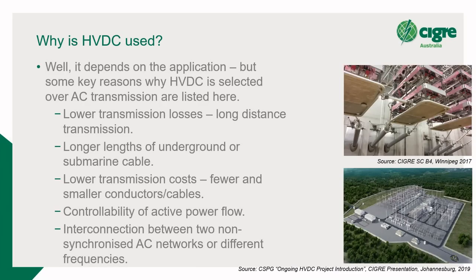Okay, so why do we use HVDC? Well, it depends on the application, but there are a number of key reasons for HVDC over, say, an AC option. Lower transmission losses is one of the big ones. So long distance transmission. So yes, the converter stations are quite lossy. The switching of power electronic devices generates heat, requires cooling, and generates heat losses. So that's a fact. The technology is improving in that area, but still compared to an AC substation, that's generally the case. But on the DC transmission side, so the cables and the overhead lines in between, the losses tend to be much, much lower.